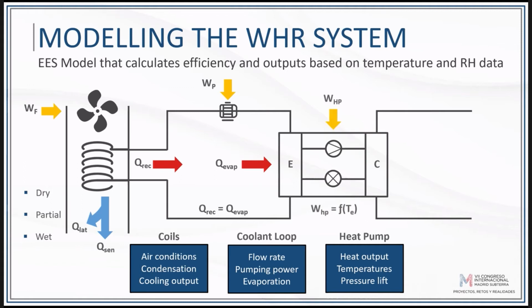Another energy balance is calculated to determine what would be the evaporating temperature for this heat pump, based on how much heat is required by the network. This lets us simulate performance for a full load condition where we deliver 1 megawatt of heat, or for a part load condition when less heat is required.